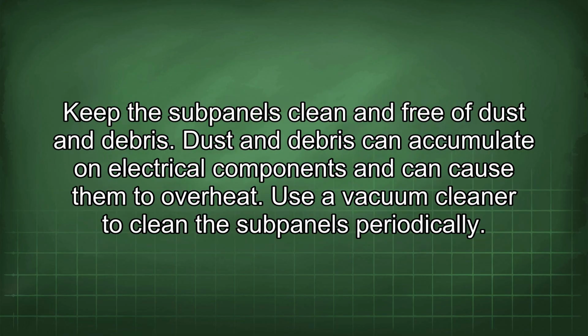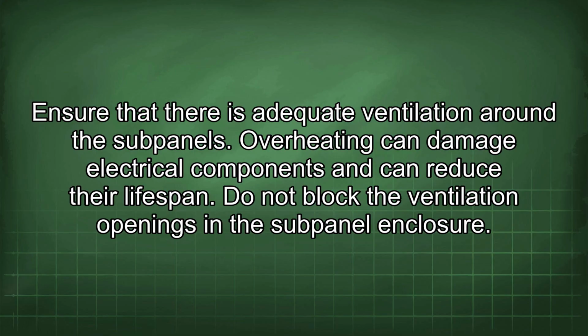Keep the subpanels clean and free of dust and debris. Dust and debris can accumulate on electrical components and can cause them to overheat. Use a vacuum cleaner to clean the subpanels periodically. Ensure that there is adequate ventilation around the subpanels. Overheating can damage electrical components and can reduce their lifespan. Do not block the ventilation openings in the subpanel enclosure.